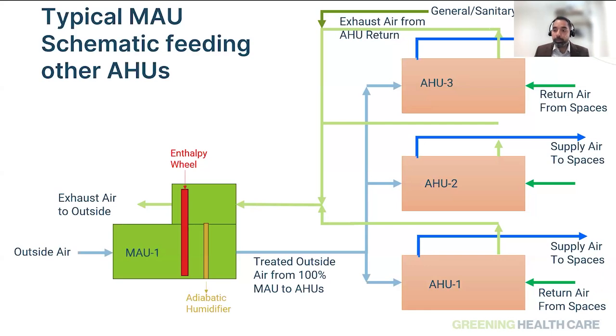However, consider a new makeup air unit, maybe on the roof, in the penthouse, or where there's space, that takes all the exhaust from those plenum areas, takes the heat from it, and then reuses or rejects that heat into an outside air plenum using a makeup air unit. You could use that combination approach with a single unit. So rather than retrofitting each of these units, you can put in one unit that takes all that exhaust and all that intake and conditions that space. These retrofits are going to become important for your facility where replacing the traditional unit is not practical because of size limitations. Thinking outside the box will help you make sure you have exhaust heat recovery embedded into your system and you're maximizing the use of it.